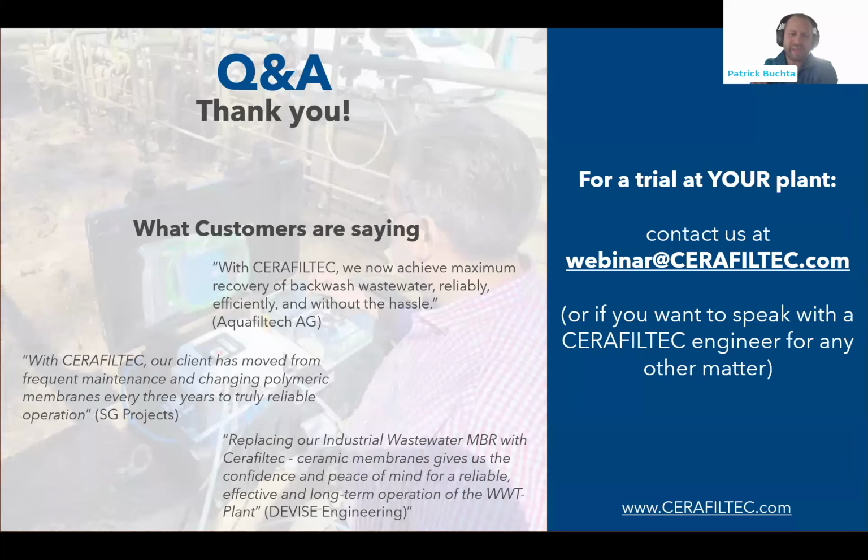It's always difficult to give a clear answer on that, especially without knowing about the organics in the water, or COD or DOC. But I would say something in the range of 100 to 150 LMH, to make it short. Excellent. And then we have an inquiry about a specific project for a specific region. It's one of our projects over 100 MLD in India. What's the status there? I think we are operational for about 50%. The remaining 50% is still in commissioning, but we're happy to talk more in detail if it's helpful.